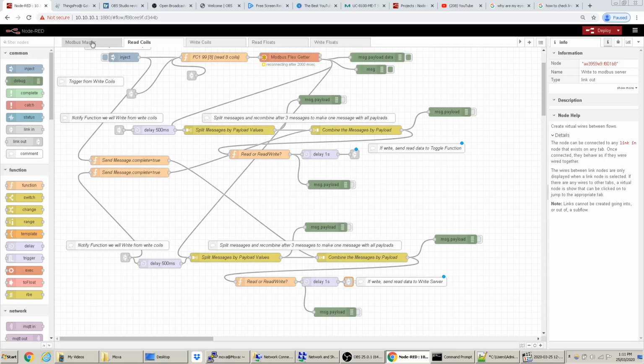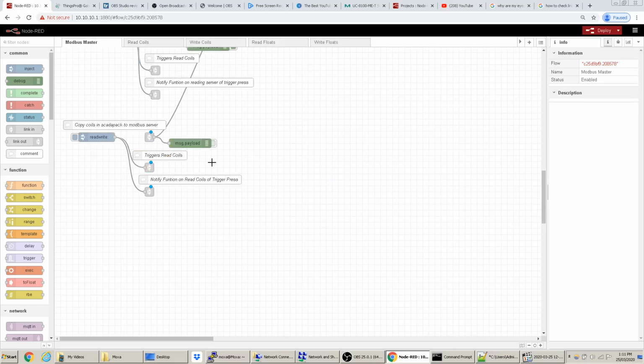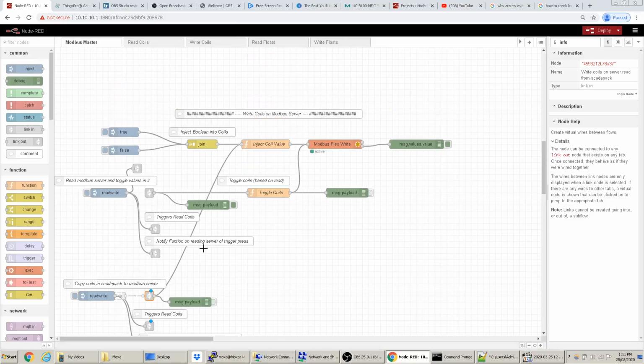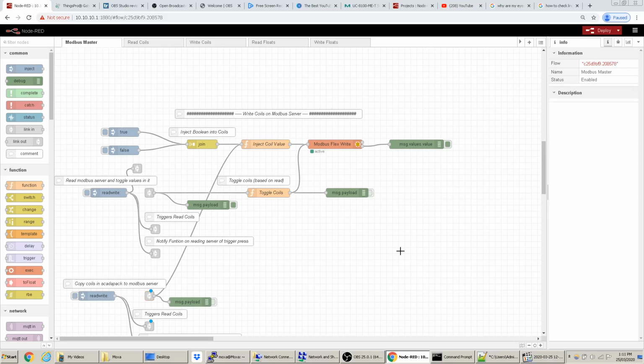Then it sends it back to this, write coils on server from Scadapack, which is right here. So it goes right here. This is write to Modbus server, and now this goes up. Boom, and it writes those values to the Modbus server. So after that operation, the values in the Modbus server are the same as the values in the Scadapack.